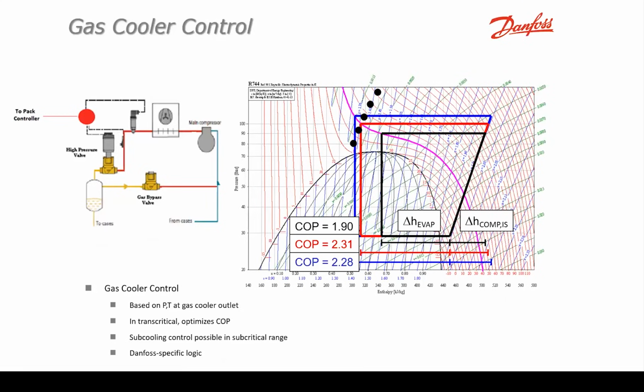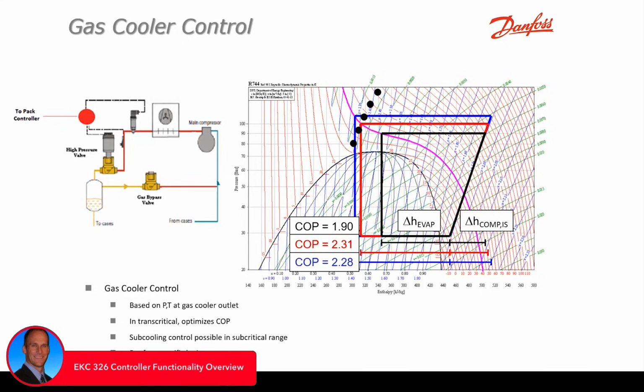I've got some slides here as talking points, and the first one is a kickoff to say that when we talk about the high pressure side of the system and what the 326 could do, it wasn't the whole system. It wasn't the compressors or the gas cooler fans or anything down at the case level. The 326 was very specific to two parts of the system. It was the high pressure valve coming out of the gas cooler, depicted on the left side of this system drawing. And a typical booster system would also have a flash gas bypass valve coming off the receiver to maintain proper pressure there and, in original designs, dump some of that vapor out of the receiver back into the suction line. Maybe there are other things today that have evolved, but that's to bypass the vapor out of the receiver. Most of your audience probably has a good understanding of that, but just so we're all on the same page, those are the parts of the system that the EKC 326 was meant to take control of.